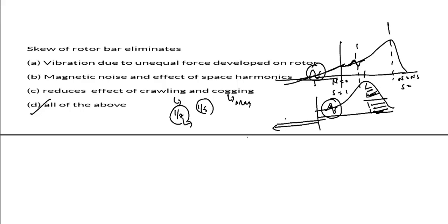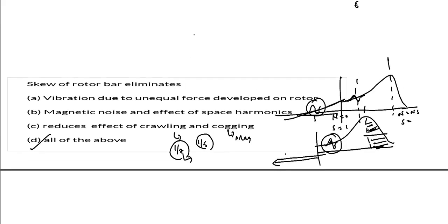Okay, cogging means magnetic locking due to the slot harmonics. So skewing of the rotor is used to eliminate the noise and vibration from the harmonic torque. Suppose I have skewing, what is skewing? Suppose this is the rotor slot. You have rotor slots here, with bars, conductors like this. So you do not place them parallel. You have some inclination.